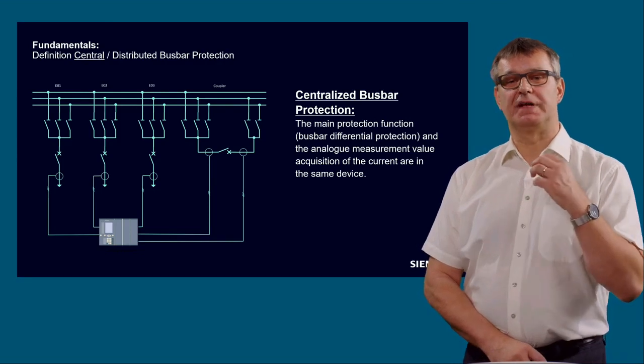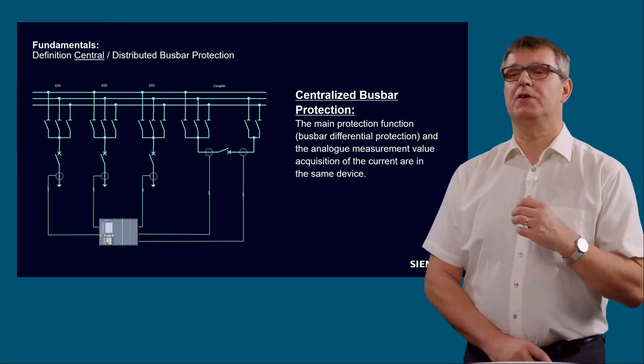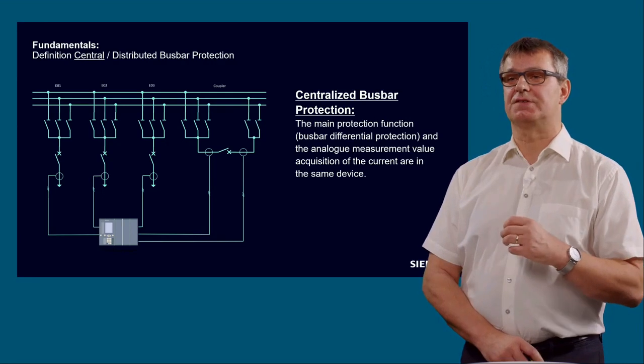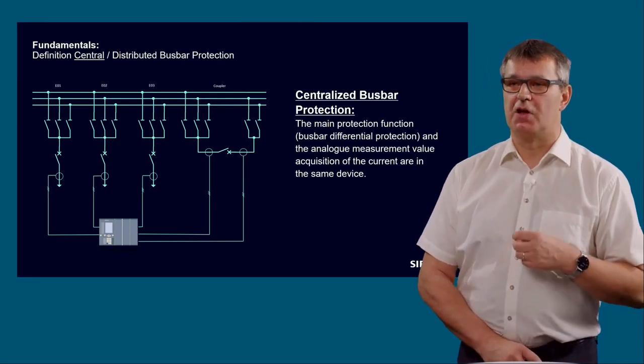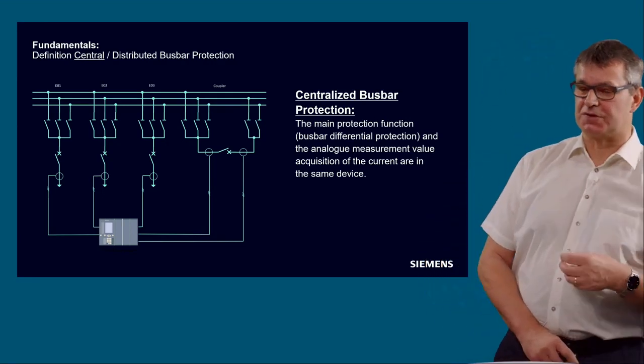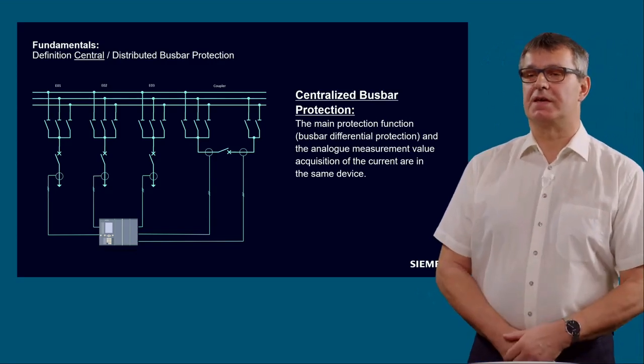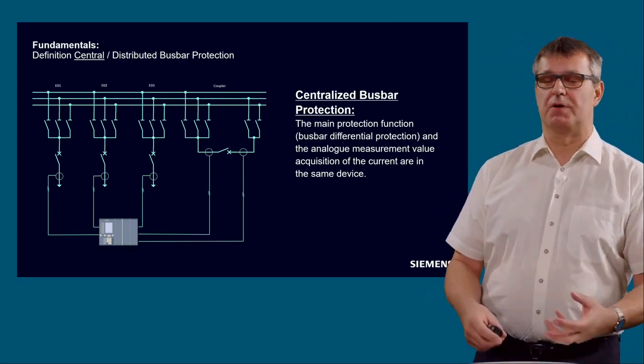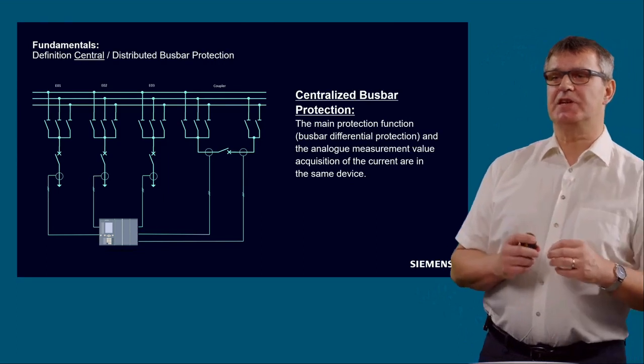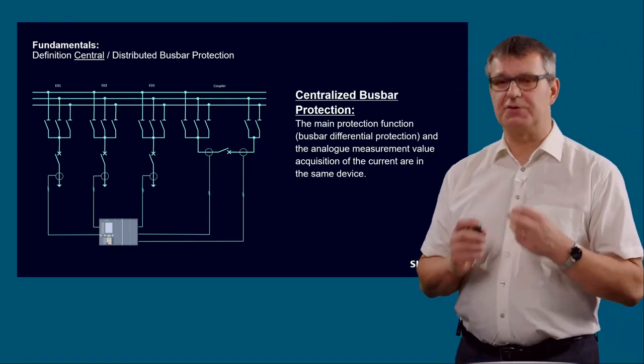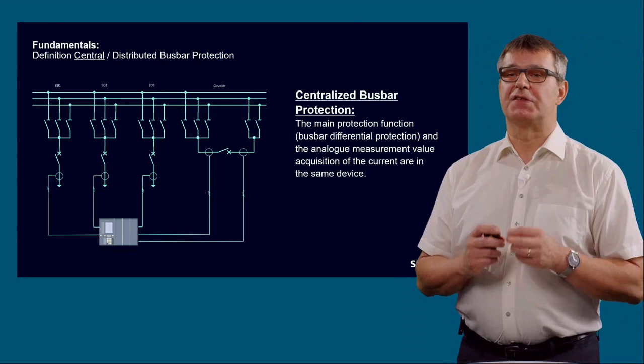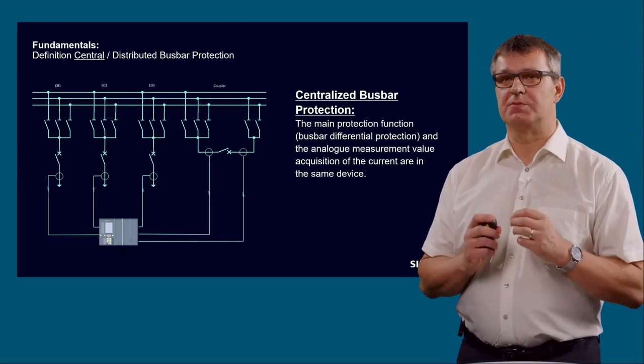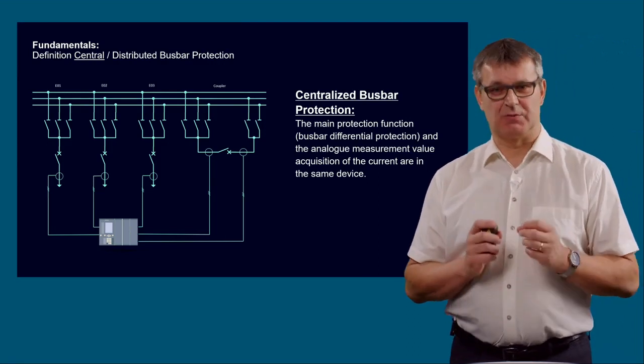It's important to understand it doesn't matter where the binary signals, the disconnector position, the circuit breaker position, and the trip commands are acquired or sent from. Essential for a centralized busbar protection is that the analog current measurement acquisition is in the same device.